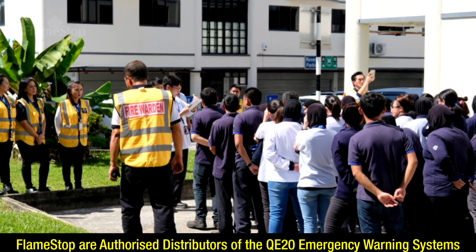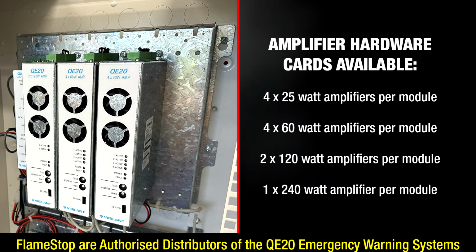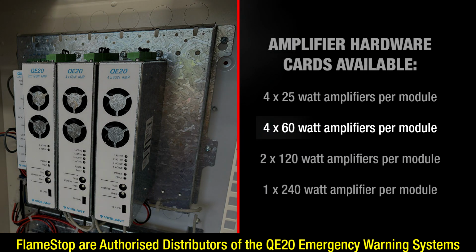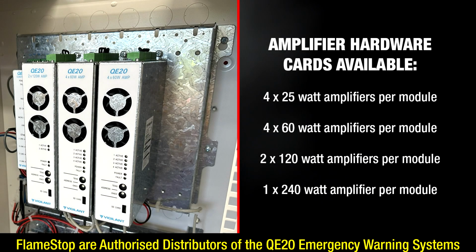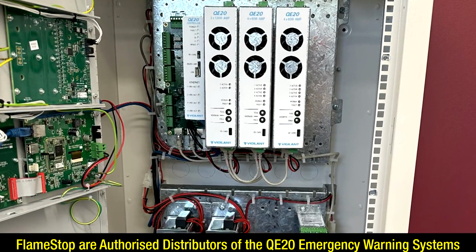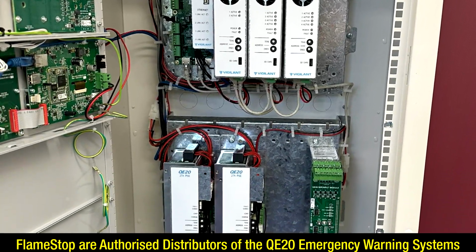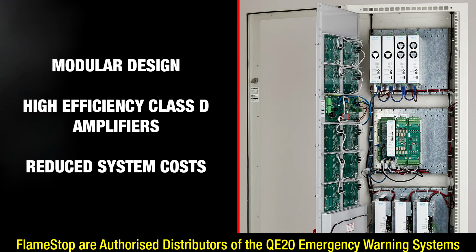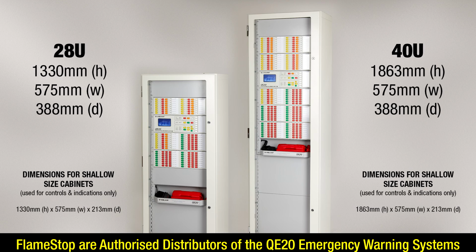event of an emergency. The QE20 has a choice of 25, 60, 120 and 240 watt digital amplifiers. Multiple amplifiers may be allocated to individual zones for greater power. The amplifiers are modular and take up less space inside the cabinets. The new high-efficiency Class D amplifiers minimise heating in the cabinet and provide greater density, therefore reducing system costs. 40U and 28U cabinet sizes are available for QE20 systems.